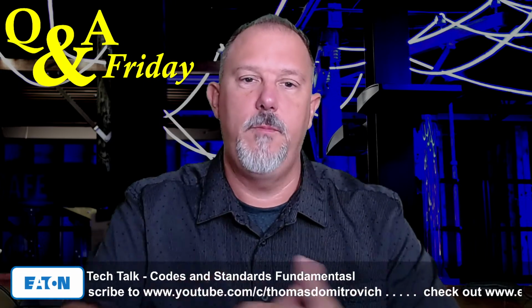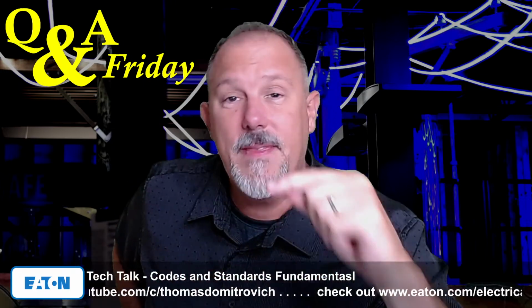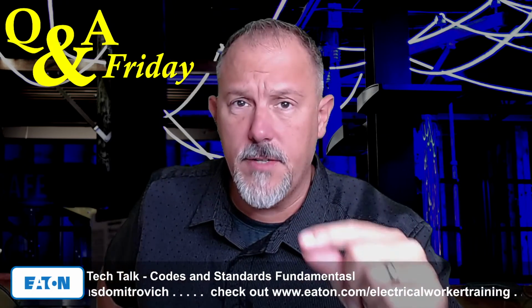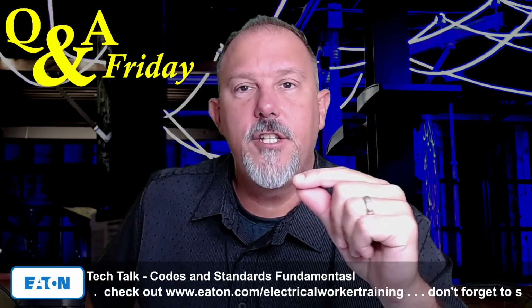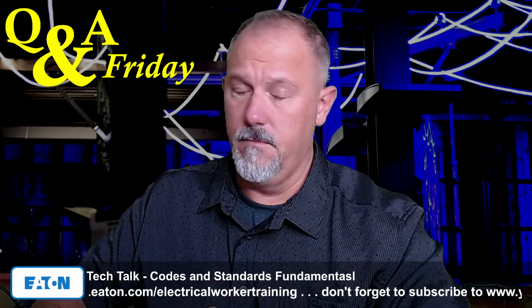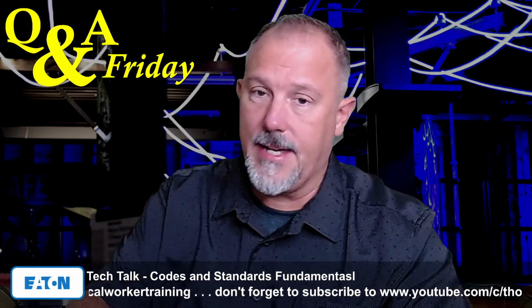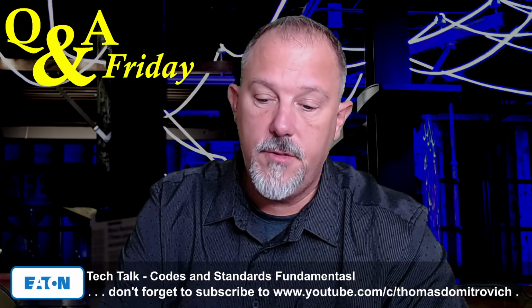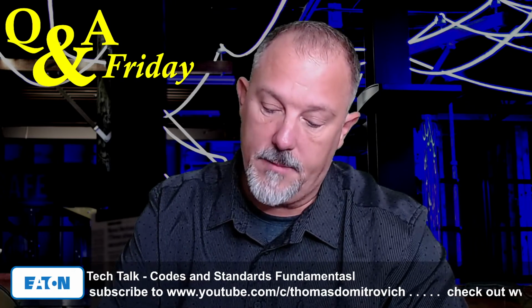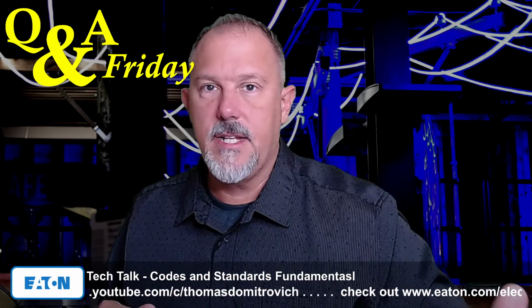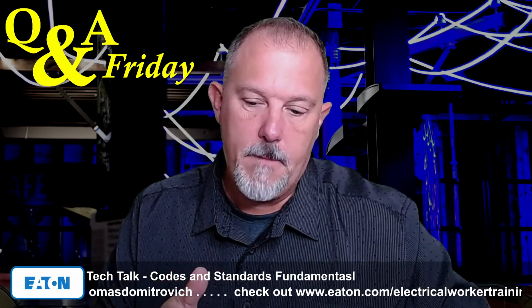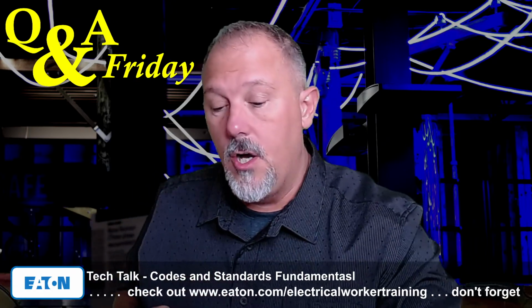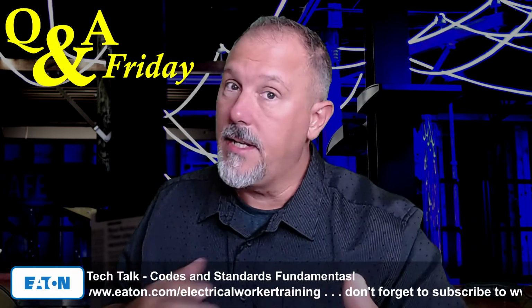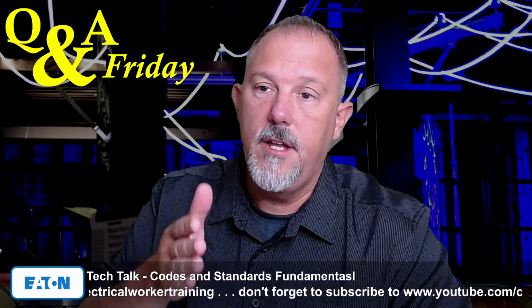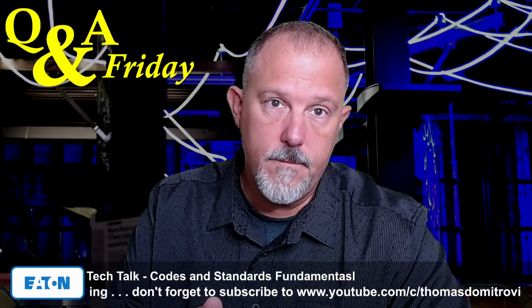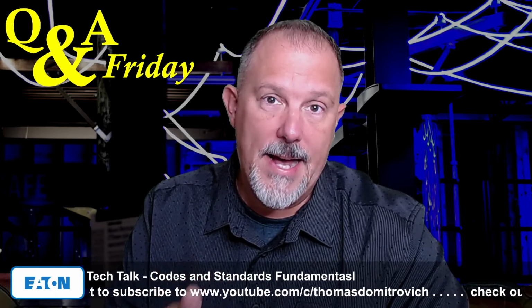If you recall, and I can't remember who made it, I don't know if it was JW or who it was, but they said, look, if I have a 2000 amp circuit breaker and I adjust the long time pickup to 1600 amps, and if I take 0.8 times a 2000 amp circuit breaker, 0.8 times 2000 is 1600 amps. The question was, if I take a 2000 amp circuit breaker, adjust it to 1600 amps, and I put 1600 amps worth of conductor on that circuit breaker, and it's only an 80% rated overcurrent device, can I use that conductor at 100% of its ampacity?